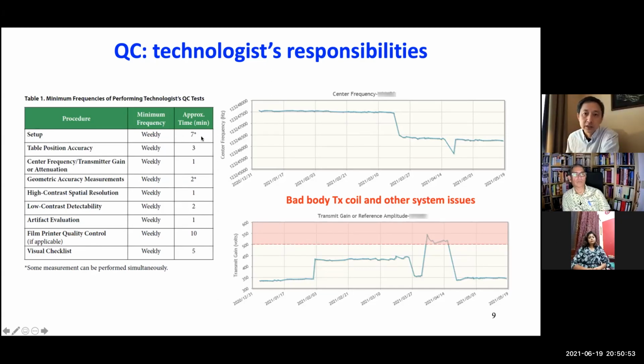At our site, and also many major academic institutions in the US, technologists only need to perform the setup part. So they set up the phantom and scan, and then push the image to a website, to a location. Then we have software to automatically process everything. So we are actually doing this daily. At MD Anderson, we have 30 clinical scanners. So on each scanner in the morning, technologists arrive at about 6 a.m.